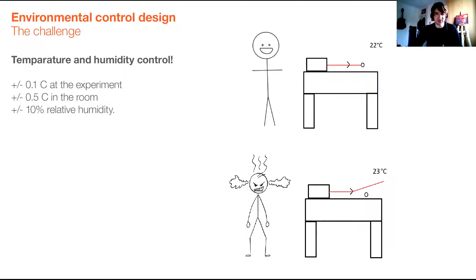So these are some photos from their existing buildings before we finished Beecroft, and this is typically how they arrange those optical experiments. They put the ion trap and the lasers on a table, and then they typically put an enclosure around the table, and the main purpose for that is to keep the environmental conditions at the experiment as close as possible, and also it saves them having to over air condition the whole room when it's just that one area they want to keep stable. They did say that it's at the experiment where it's critical to have the temperature control. They weren't really that bothered about the 0.5 degrees C temperature swing in the lab, as long as they had temperature stability at the enclosure. But they didn't want an oscillation in temperature in the lab causing an oscillation in temperature at the experiment.